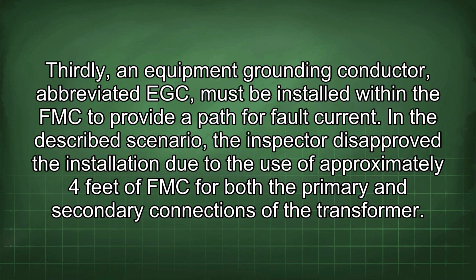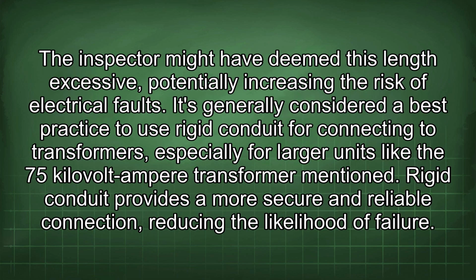In the described scenario, the inspector disapproved the installation due to the use of approximately 4 feet of FMC for both the primary and secondary connections of the transformer. The inspector might have deemed this length excessive, potentially increasing the risk of electrical faults. It's generally considered a best practice to use rigid conduit for connecting to transformers, especially for larger units like the 75 kVA transformer mentioned. Rigid conduit provides a more secure and reliable connection, reducing the likelihood of failure.